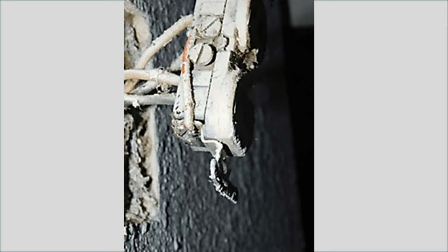Before I go to my test board, let me show you real quickly what a bootleg ground is. So this is a picture of one I found on an inspection once. It's kind of hard to see, but there's a red wire in that picture that's vertical that's going from the neutral screw to the ground screw. That's the jumper that's creating the bootleg ground.